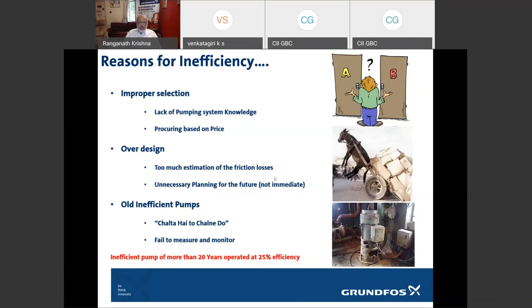But any building or any factory does not go into full production on day one. So people buy pumps which are sized for full production, just one pump or two pumps, one working, one standby. And then you start running them before the factory or the building gets occupied, which may take a year or two or three. You will be running pumps so inefficiently that you will lose a lot of money. A better way of doing it is to have multiple pumps which switch in and switch out, or perhaps leave a place for adding pumps in the future so that you can add them as and when you require.